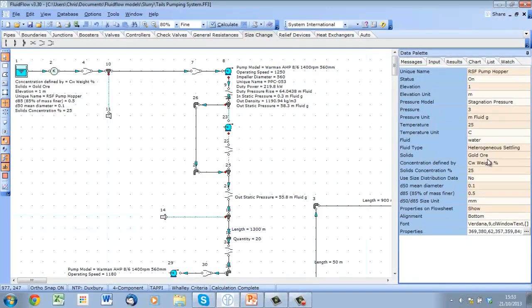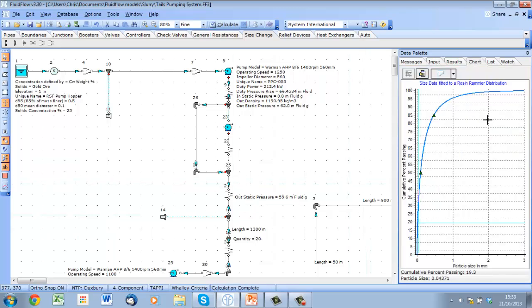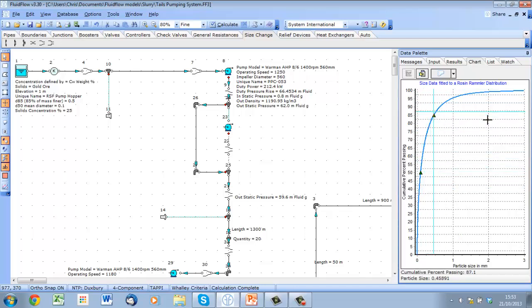On the input tab, slurries are defined in the same manner as they always have been: specify a solid, a concentration, and a particle size distribution. Another exciting new feature in version 3.3 is the ability to create a Rosin-Rammler particle size distribution from D50 and D85 values. This allows all the methods to be used with the often minimal data available at the start of a project.